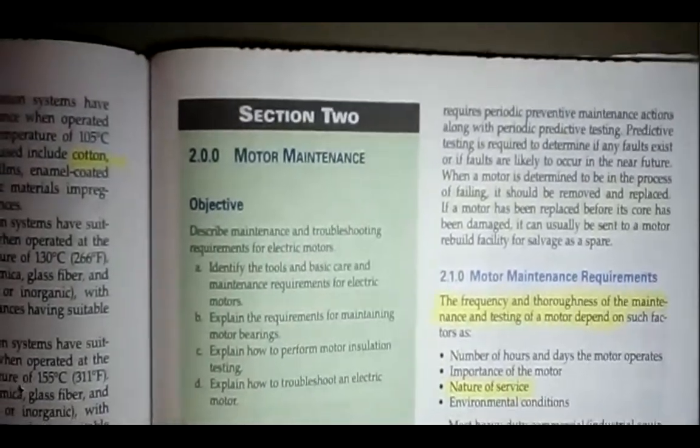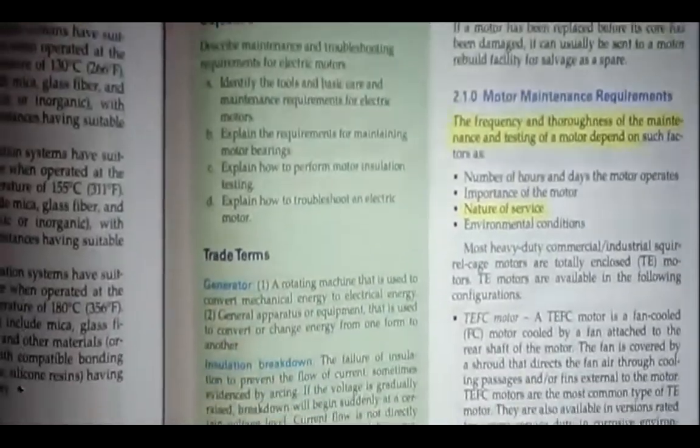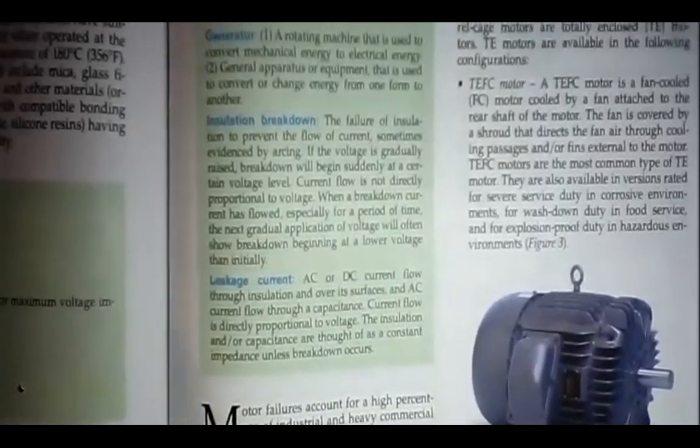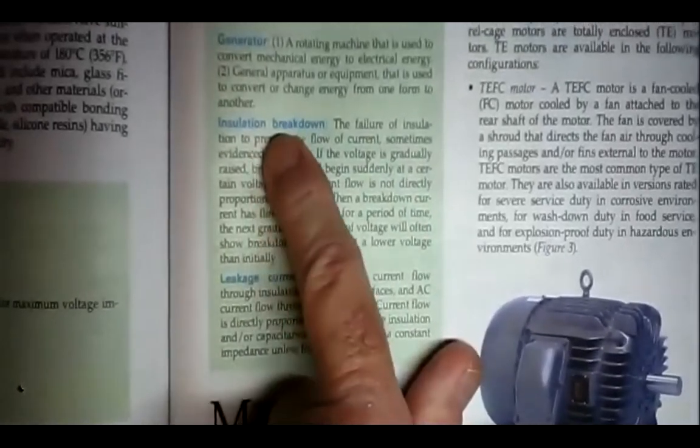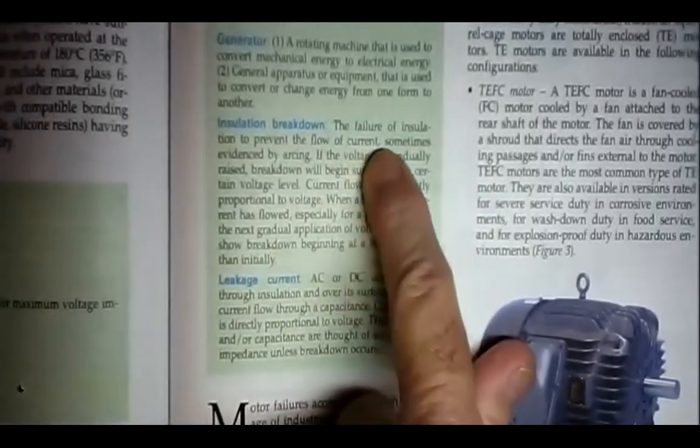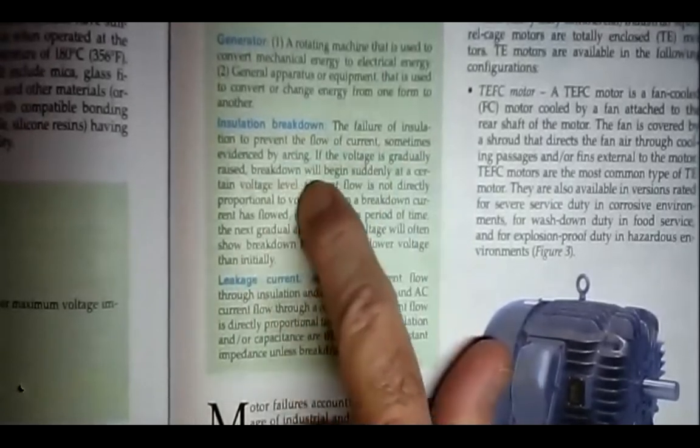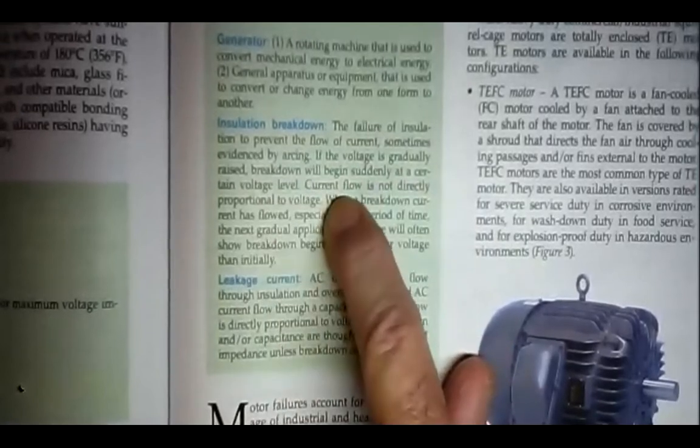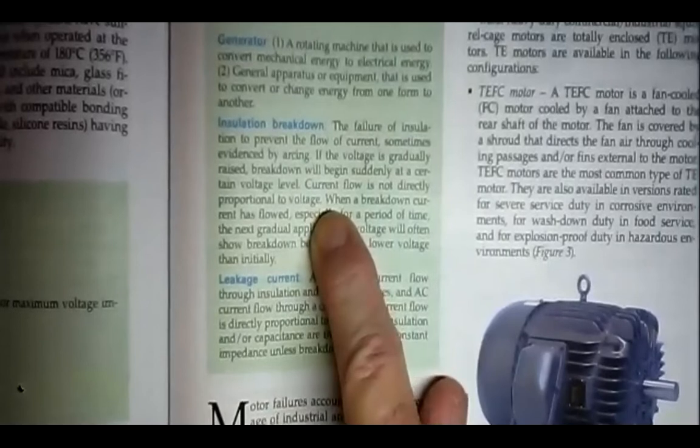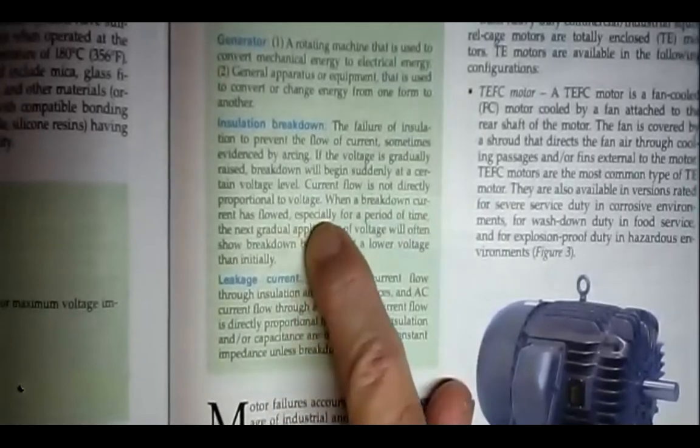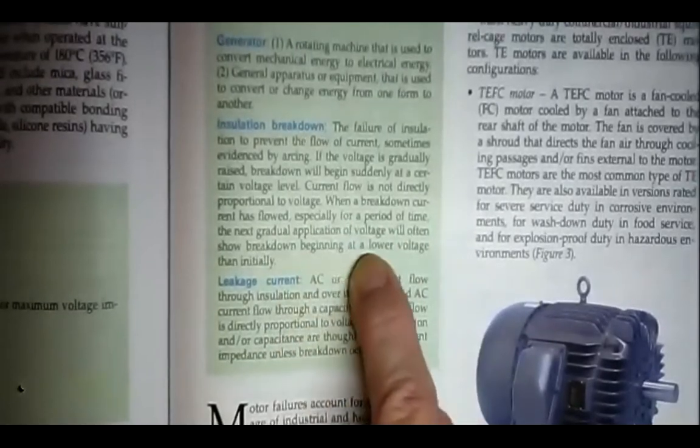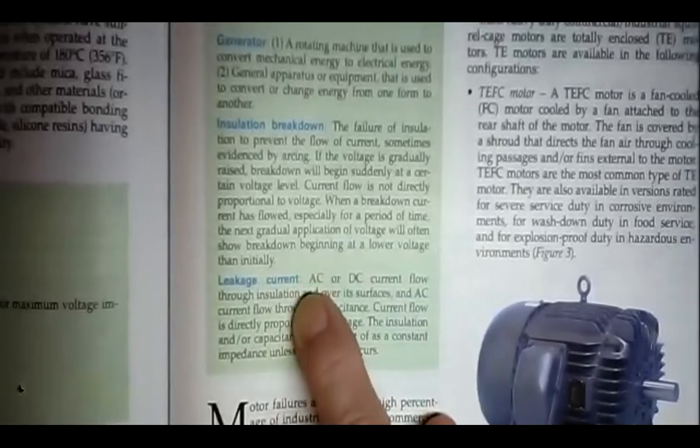Motor maintenance on page 7. Again, they have trade terms. You should stop at every section and read the trade terms. Insulation breakdown. I think that's a Led Zeppelin song. The failure of insulation to prevent the flow of current sometimes evidenced by arcing. The voltage is gradually raised. Breakdown will begin suddenly at a certain voltage level. Current flow is not directly proportional to voltage. When a breakdown current has flowed, especially for a period of time. The next gradual application of voltage will often show breakdown beginning at a lower voltage than initially.